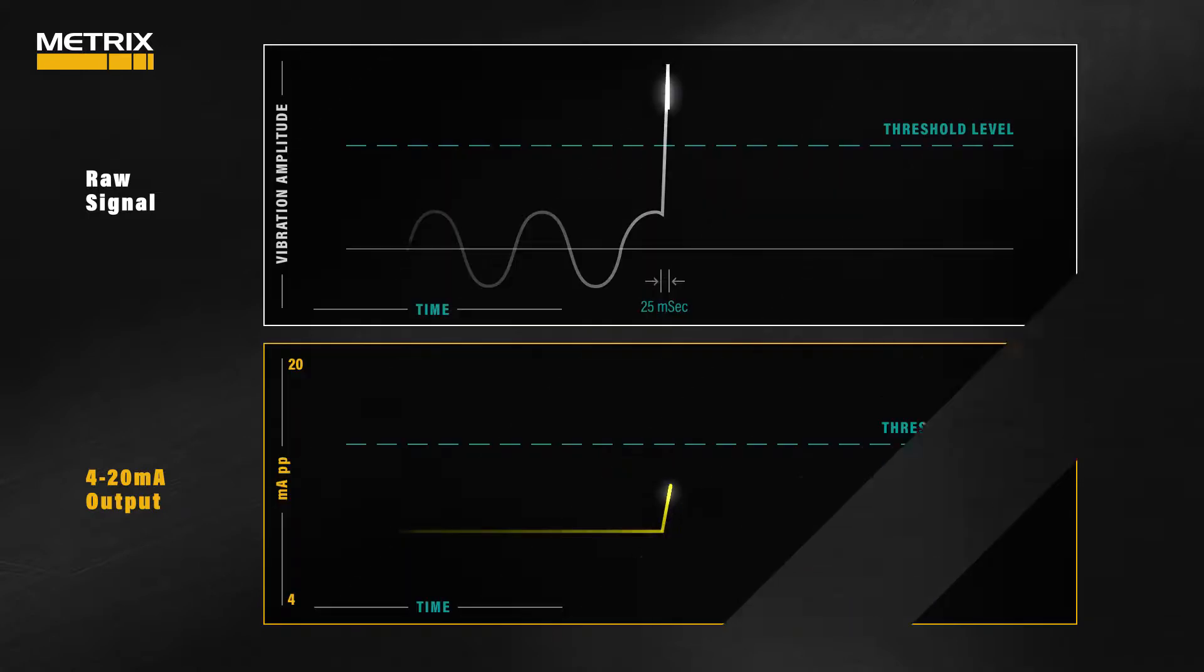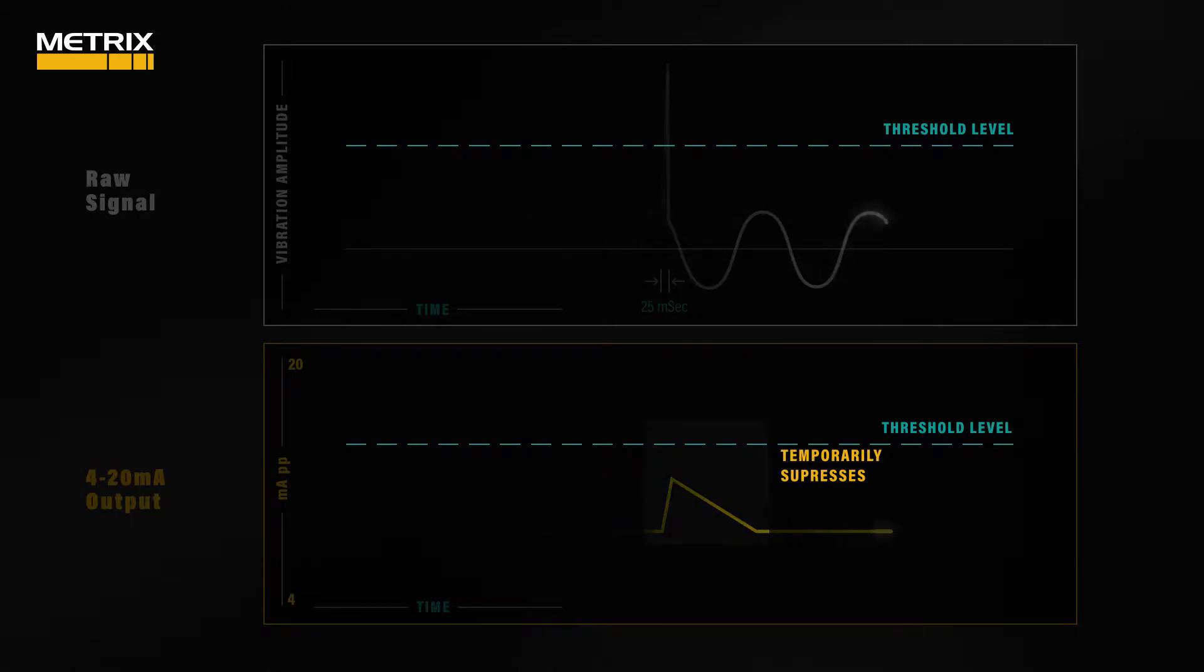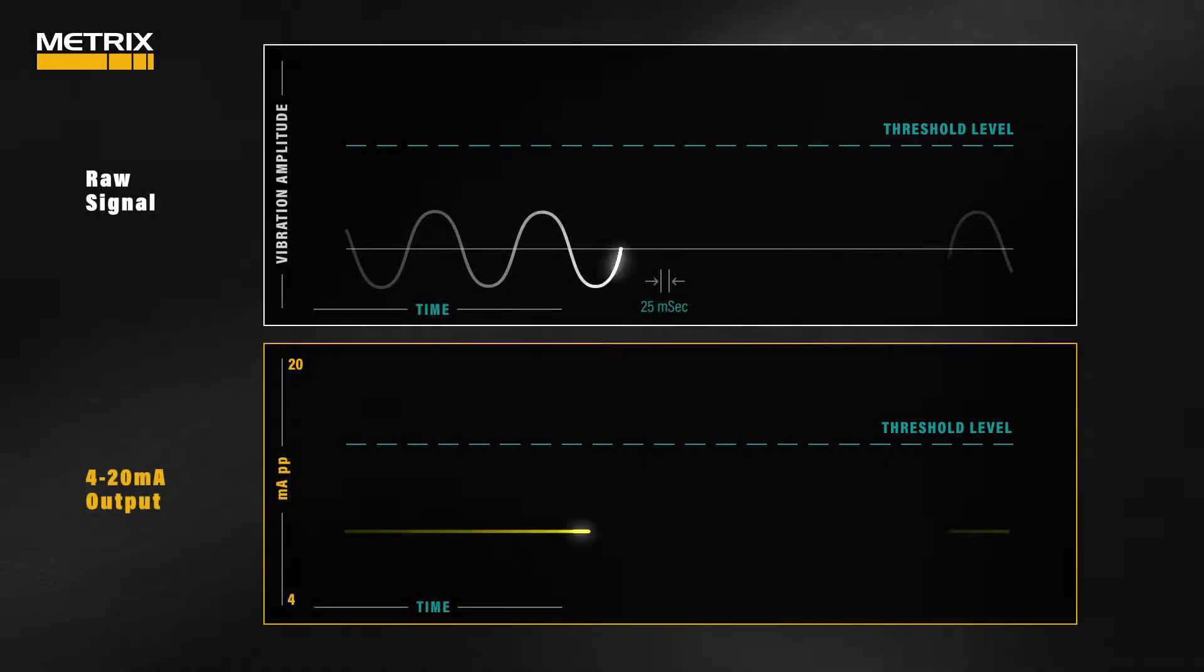or other electrical transients. This feature temporarily suppresses the 4 to 20 milliamp output during high amplitude short duration single polarity vibration spikes to prevent spurious alarms and false shutdown signals.